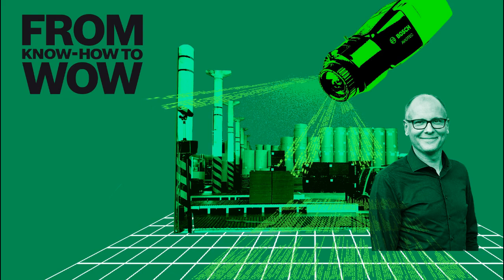Smoke can take minutes to reach the ceiling. Søren says it could take quite a long time, and he's even seen cases where the smoke doesn't actually rise to the ceiling at all — it creates a layer within the building, like low-hanging clouds or even a fog. It depends on how the building is heated or air-conditioned. You could have a hot layer of air under the ceiling that's actually hotter than the smoke of a fire that had just started, and so the smoke lingers underneath that hot air. But for Aviotec, that doesn't matter — it's a visual system. If you can see a flame or smoke, Aviotec can see it as well.